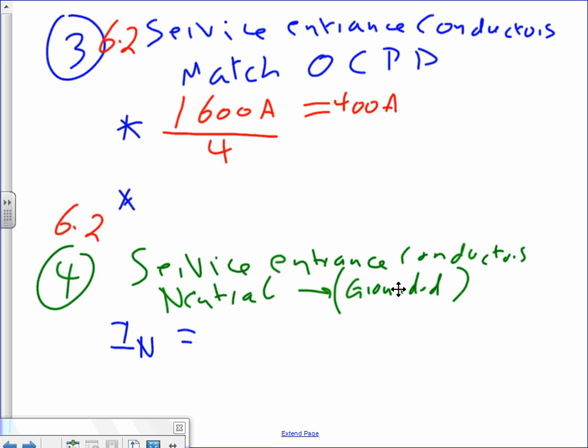So how many sets am I running in different conduits, paralleling? Do you guys know what paralleling is? At the end, they take the 4 conductors of phase A and tie them together like this, and they attach them to the breaker from one side. From the other side, the 4 conductors of phase B, tie them together and tie them to the panel or the transformer at the other end. And every phase the same way. Phase A, phase B, phase C, each phase will have 4 conductors, and the neutral 4 conductors. Okay, so very easy, piece of cake.